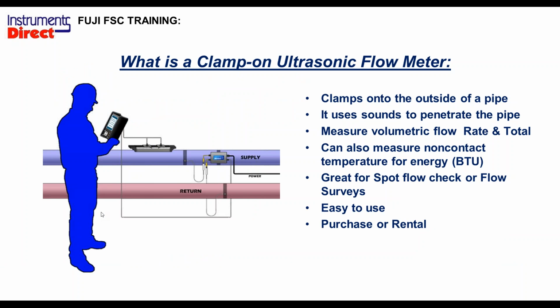So for those new people to the world of ultrasonic flow meters, what is a clamp-on ultrasonic flow meter? What is all this noise about this technology? Well, the uniqueness of this type of flow meter is that it is non-invasive. You just clamp a sensor on the outside of a pipe, and it monitors flow on the inside of the pipe. That is the novelty of this technology. So you don't have to put a hole in the pipe. Nothing gets wet. Nothing makes actual contact with the liquid.